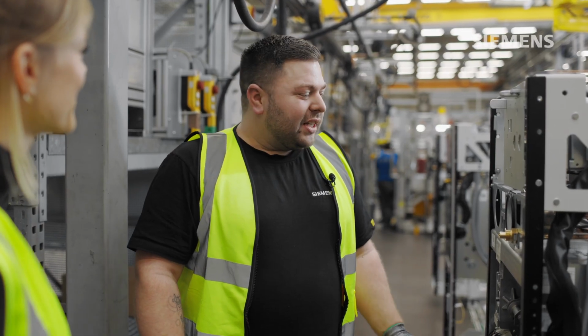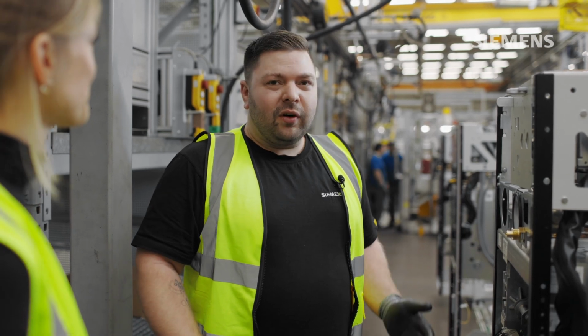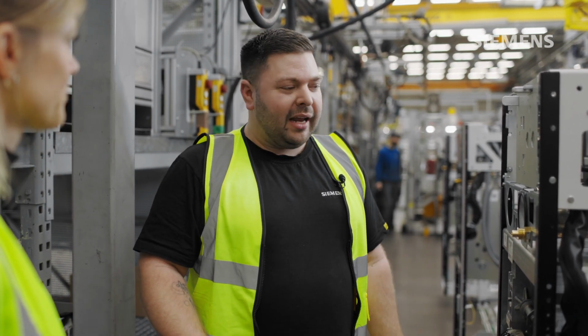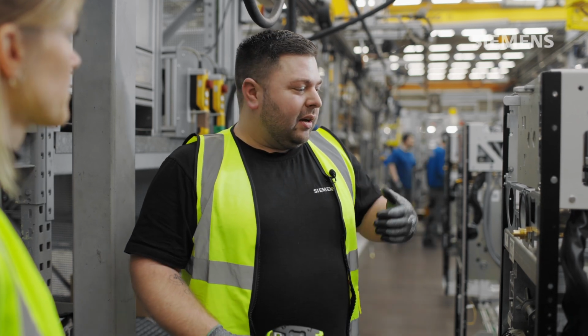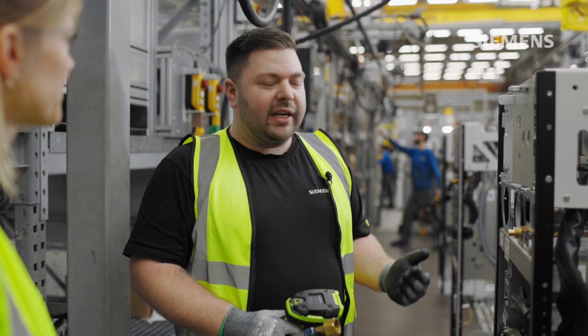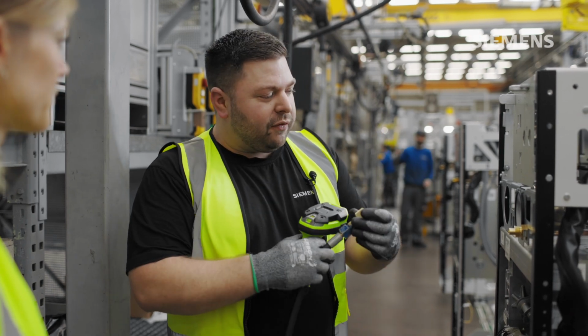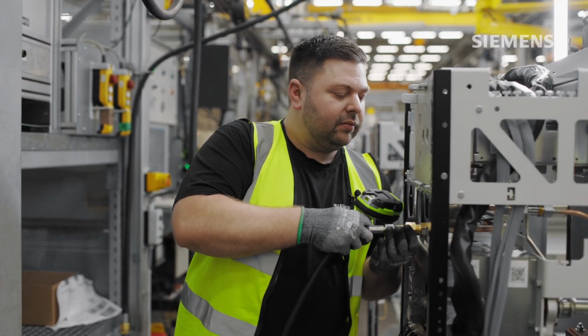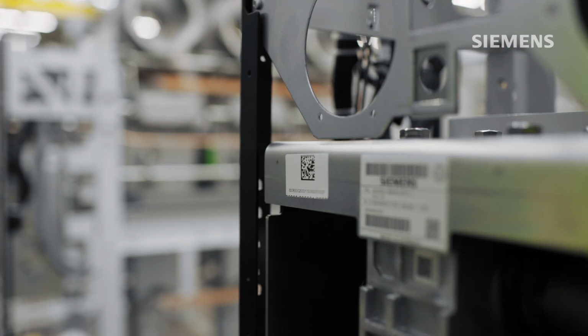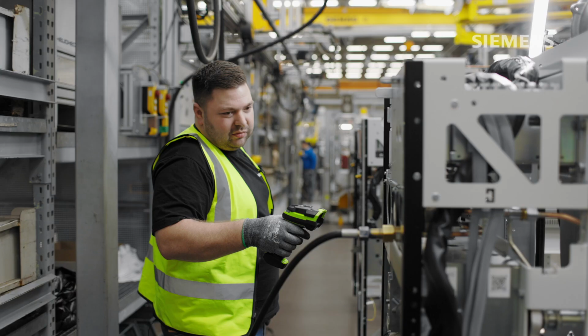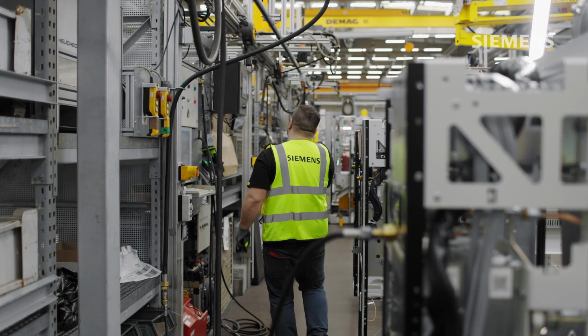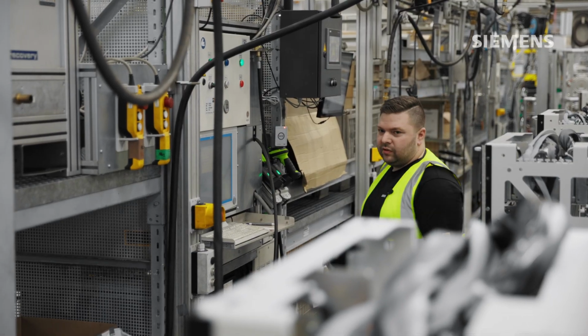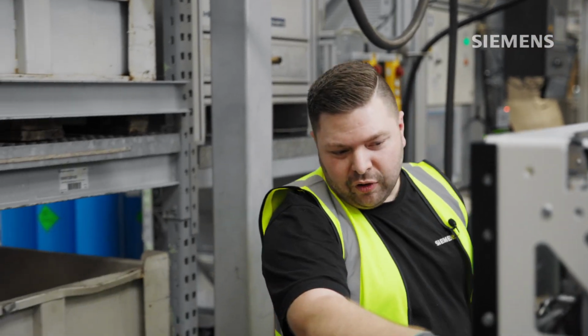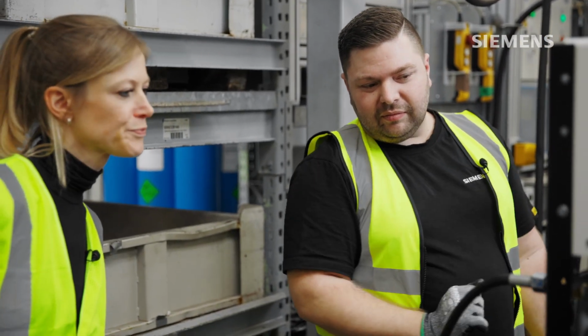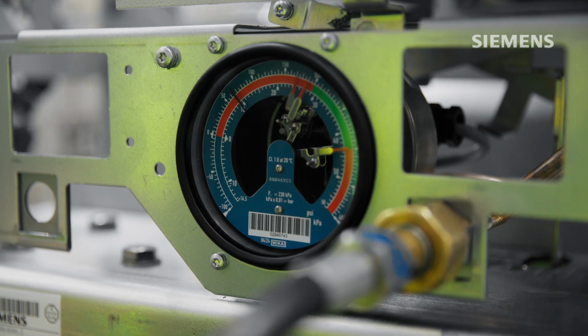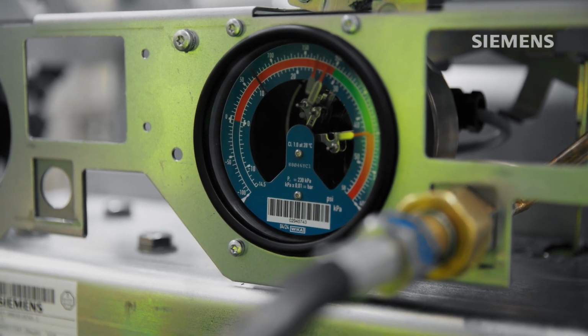Here we are now at the filling station of our assembly line for our 8DAB device. After we previously checked our field for leaks with helium, which is also recovered, we are now filling our field with insulated clean air gas. For this, I attach the filling hose to the field, scan the QR code, and start filling. Now the field will be filled with the appropriate insulating medium and the correct pressure applied.